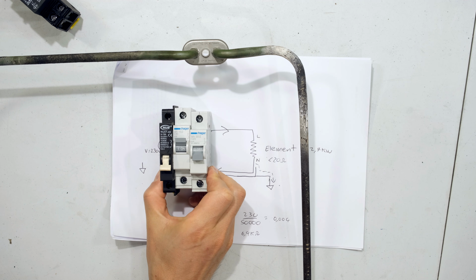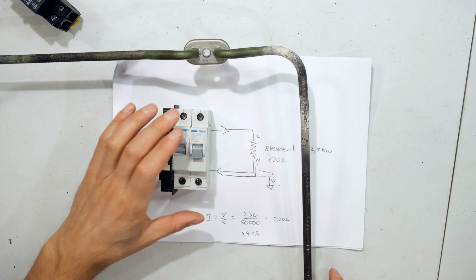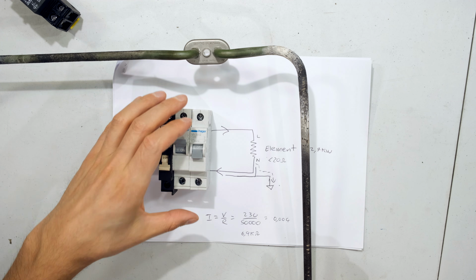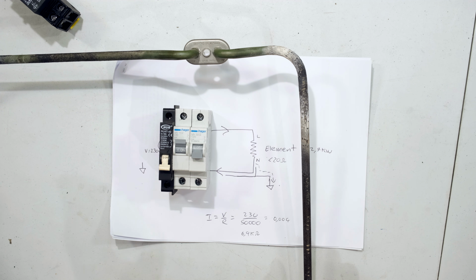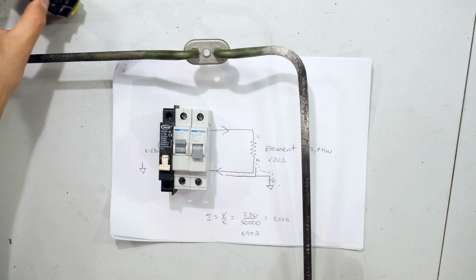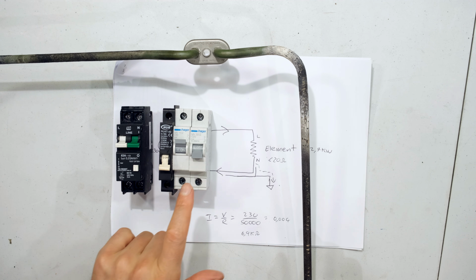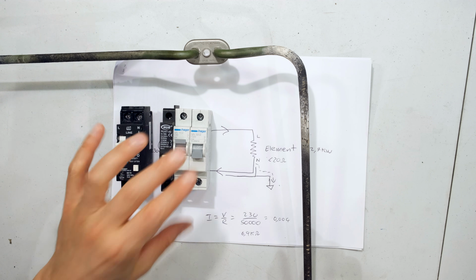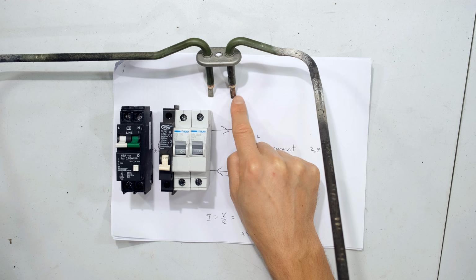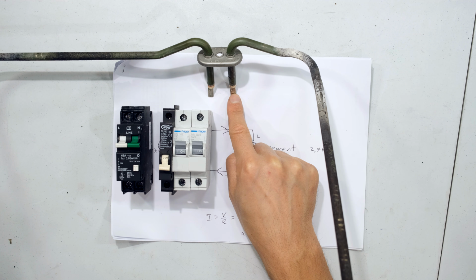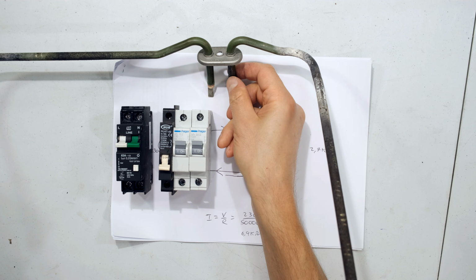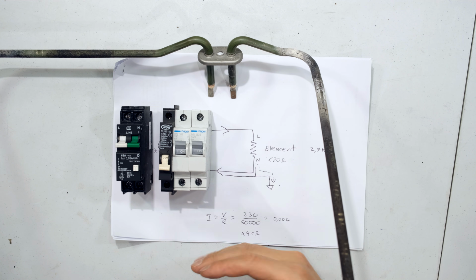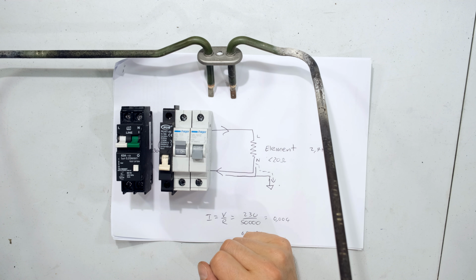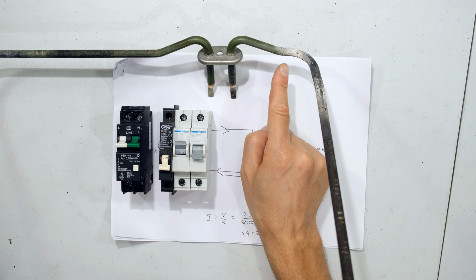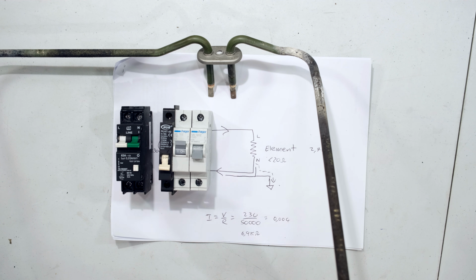It won't trip your line circuit breaker, the circuit breaker which is feeding your dishwasher, for example, because the earth leakage current in this case was only small. That is why it tripped the RCD and not the main circuit breaker, say for your oven or your dishwasher, because it's not like the element wire over here suddenly shorted onto the casing, therefore initiating a much higher current. That would trip the circuit breaker. In this case, this is a slow insulation breakdown, and eventually it actually trips the earth leakage.